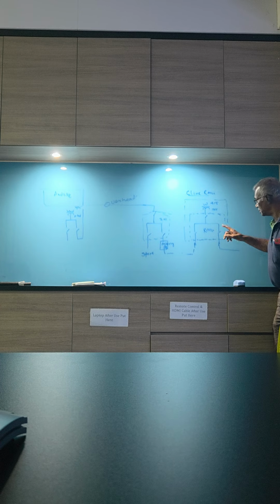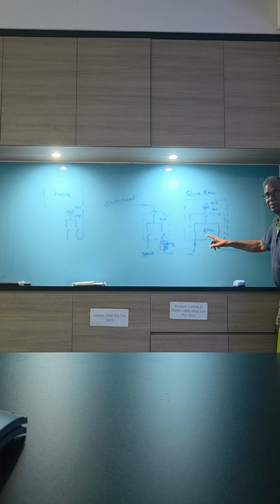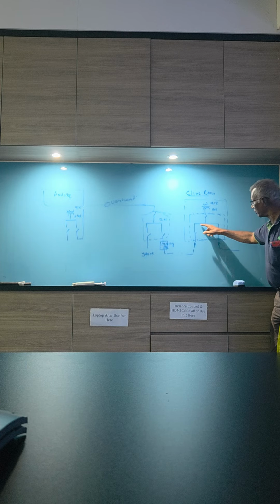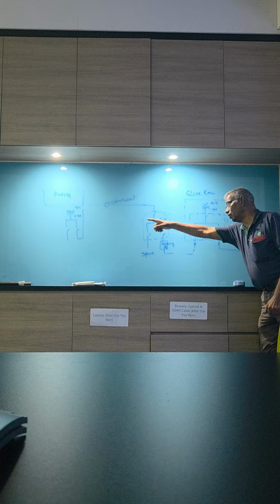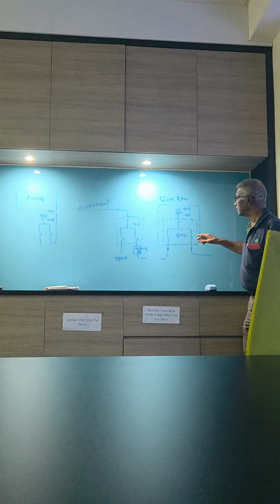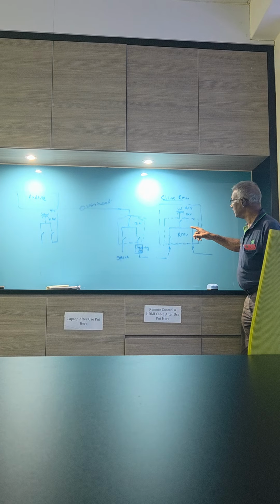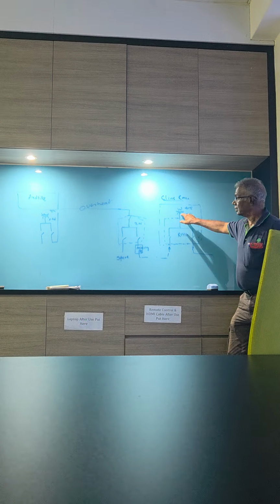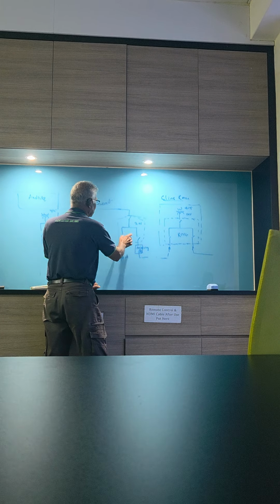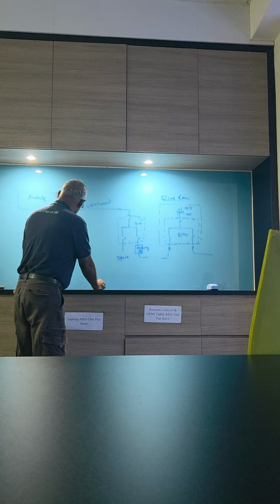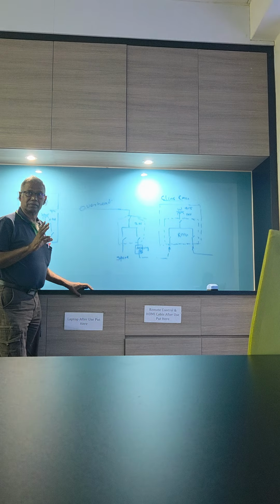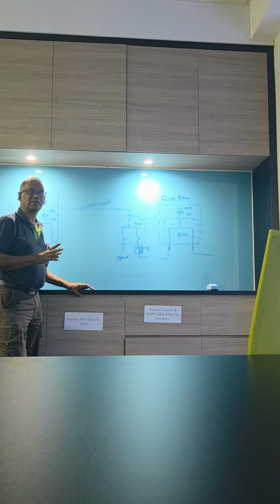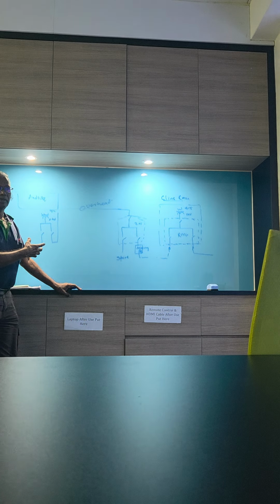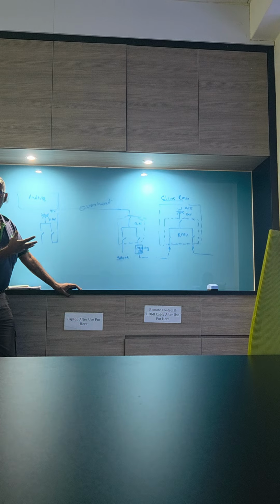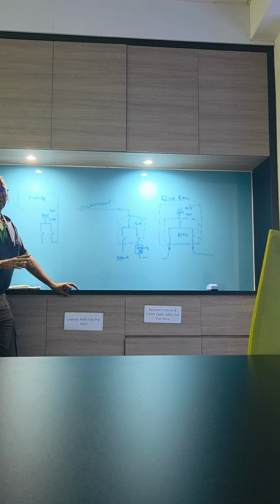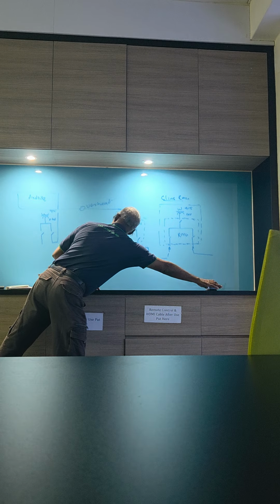Likewise, another thing, they have two incomers here. They also call it a ring main, the in and the go out. And then finally all that loops back. That's another issue. So they have a built-in protection relay only for the outgoing. Inside this I didn't see, don't know, but this one I saw. Outgoing, they have a protection relay here, but there is no external voltage given for the tripping coil. There is no external voltage, like what we have, 110, or on the HT side DC 30 volt, a battery station, right? Then it's none. So what actually is there is like this.